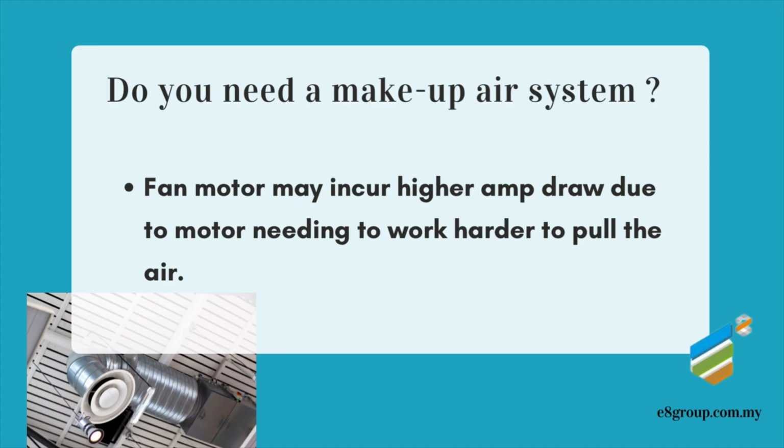You know what it does? It's very disciplined. It's going to keep pushing. It says, okay, there's no air, let's keep pushing. So it's going to start drawing more current. The motor is going to run at a higher load compared to how it was designed. So the wear and tear is going to increase. The motor basically is not going to last longer.